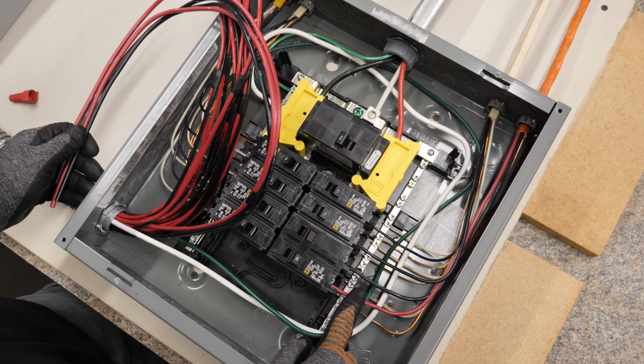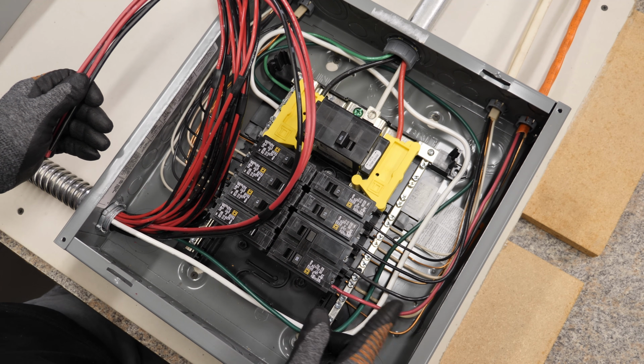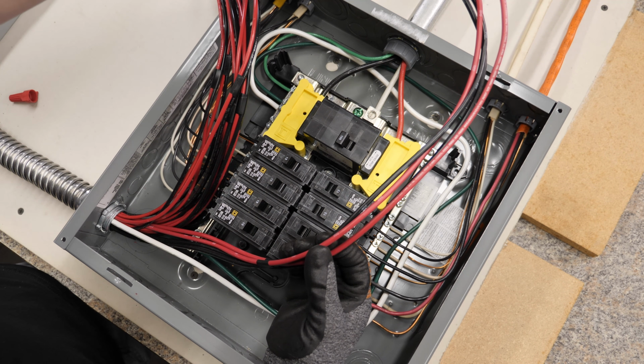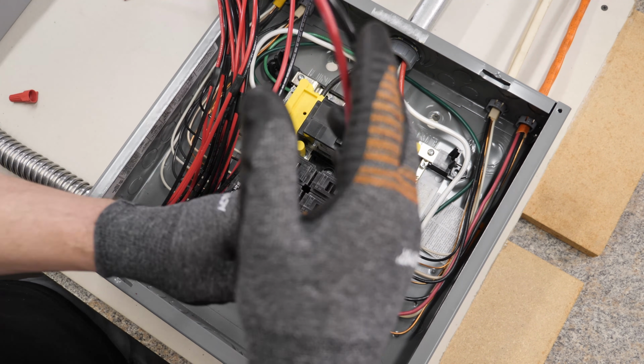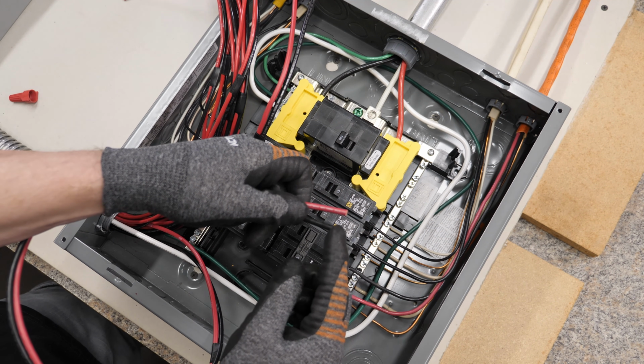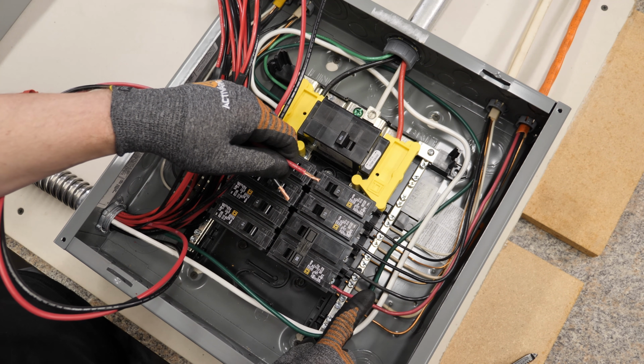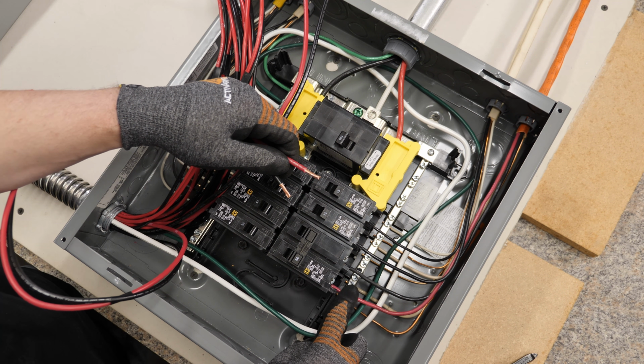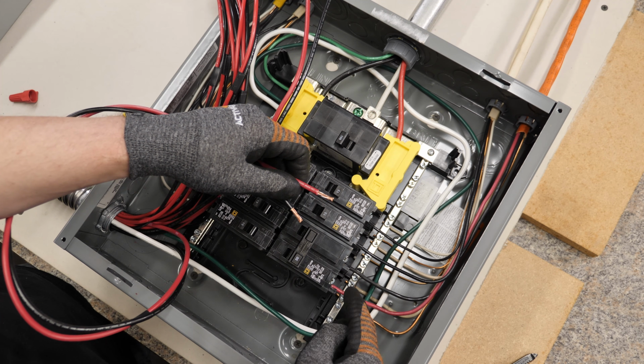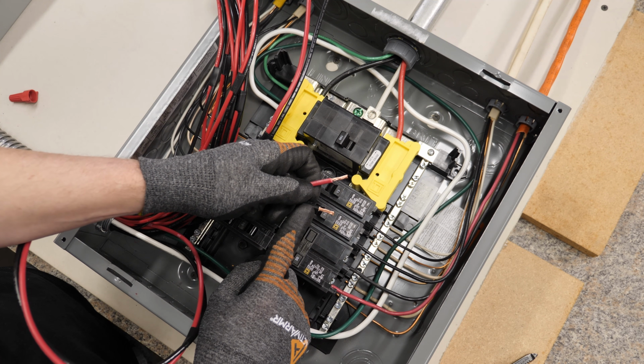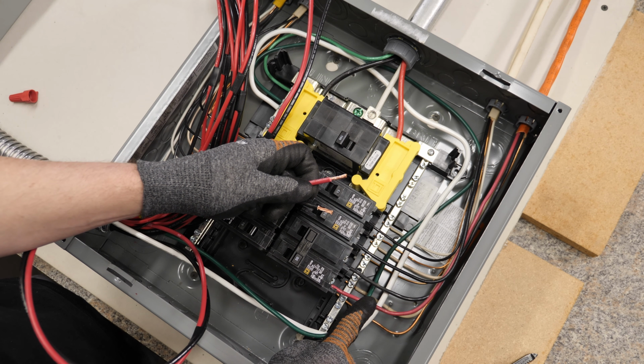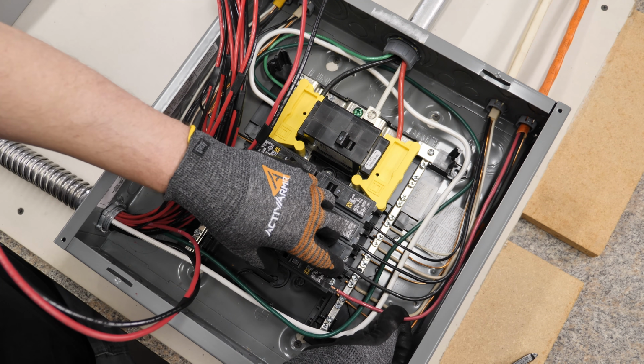We'll start with the red wire since it's the lowest one there, so we'll grab our B wires out of here and set A aside. I'm going to trim these back a little bit. First we pull off the red wire here - this red wire attaches to the circuit breaker, and this black wire attaches to the load wire. We back out the screw and remove the red wire.